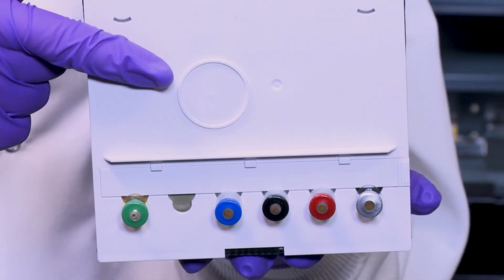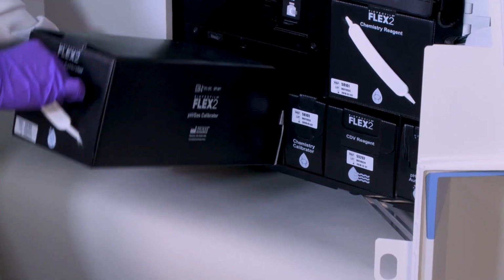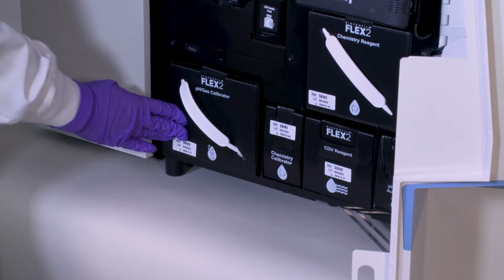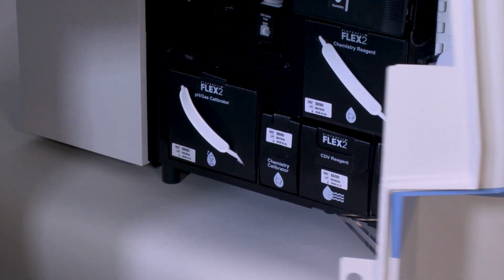Each of the reagent cartridges is equipped with a radio frequency identification, or RFID tag. This tag tells the system when a reagent has been removed or replaced. It also stores all of the use life information, including how much volume is remaining in the pack and when it will expire. Upon closing the analyzer door or doors, the system will automatically check all of the RFID tags.